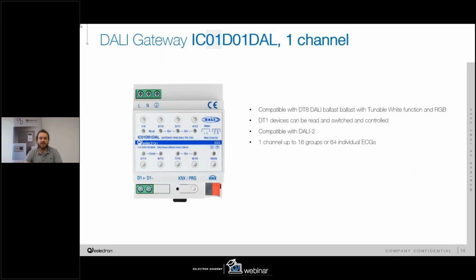Starting from the IC01D01DAL, we can wire up to 64 ballasts and group them up to 16 groups. And we can control any kind of ballast, because this gateway is now compatible with DT6 single channel lighting ballast, and also with DT8 for tunable white application, but also RGB and RGBW, for example. In addition, DT1 and DT0 ballasts used for emergency systems can be discovered, and we can control them with this gateway. This module can be useful just to control, but not to have an analysis of the emergency lighting system. And of course, it is already compatible with the DALI2 protocol.